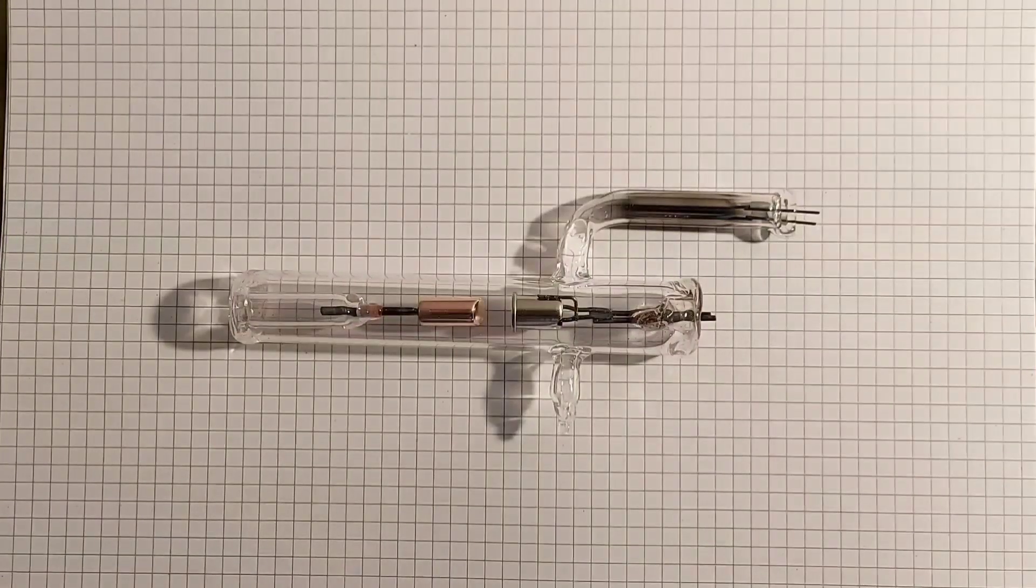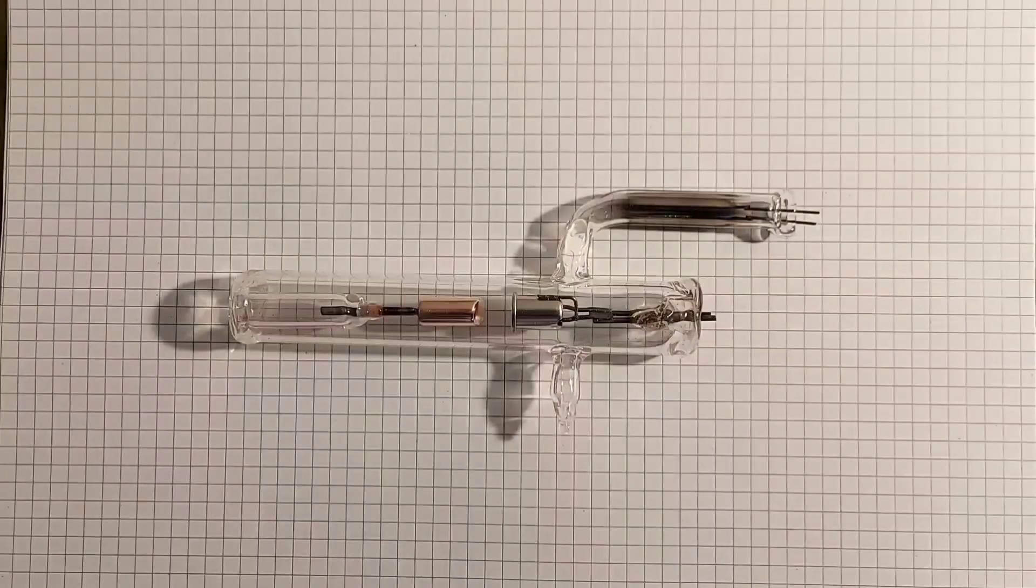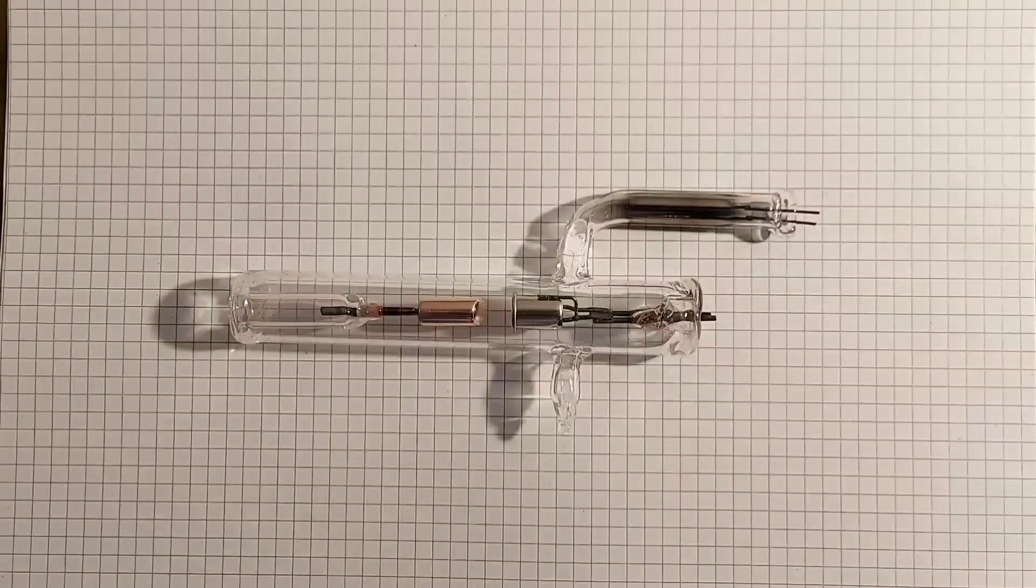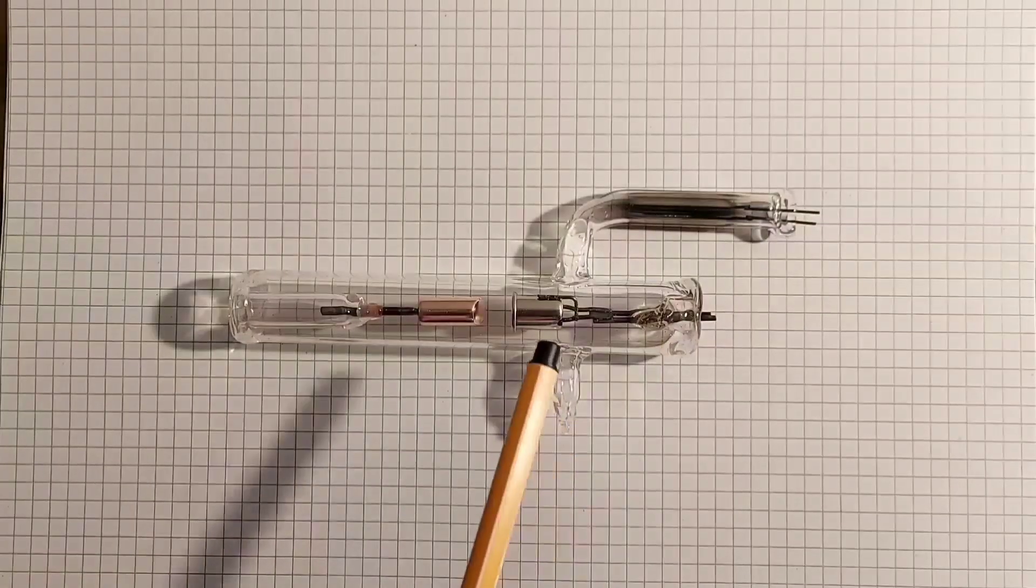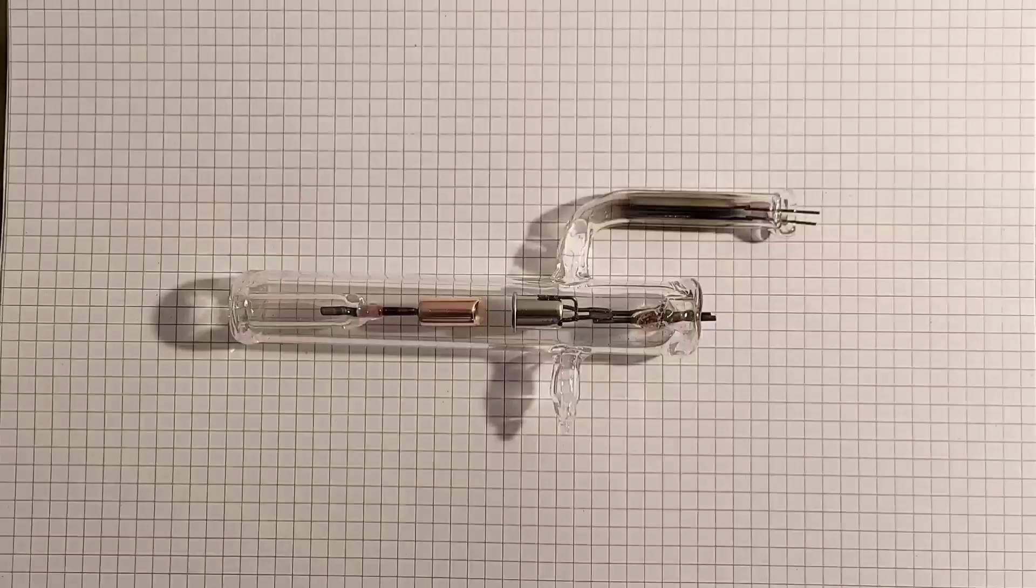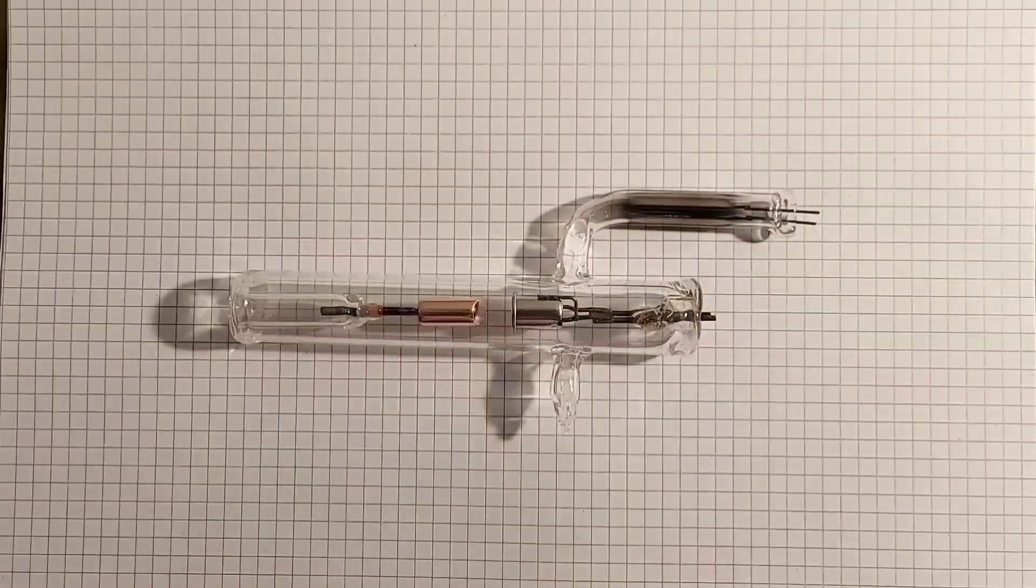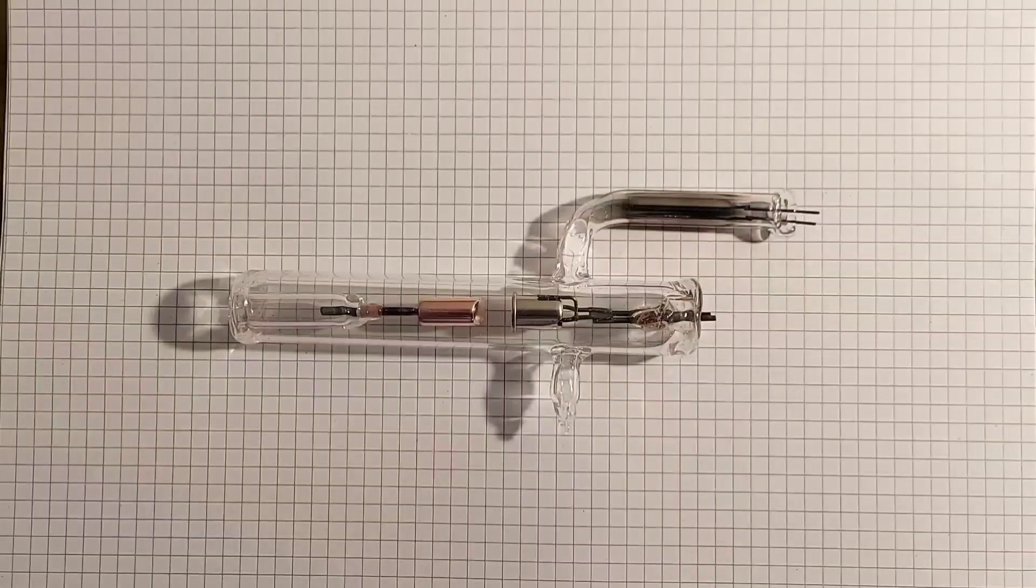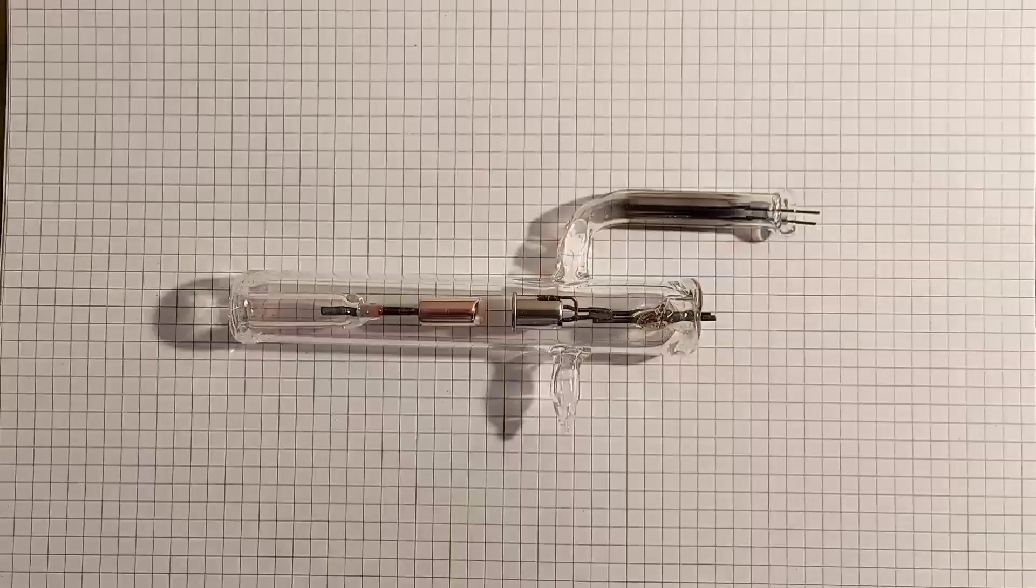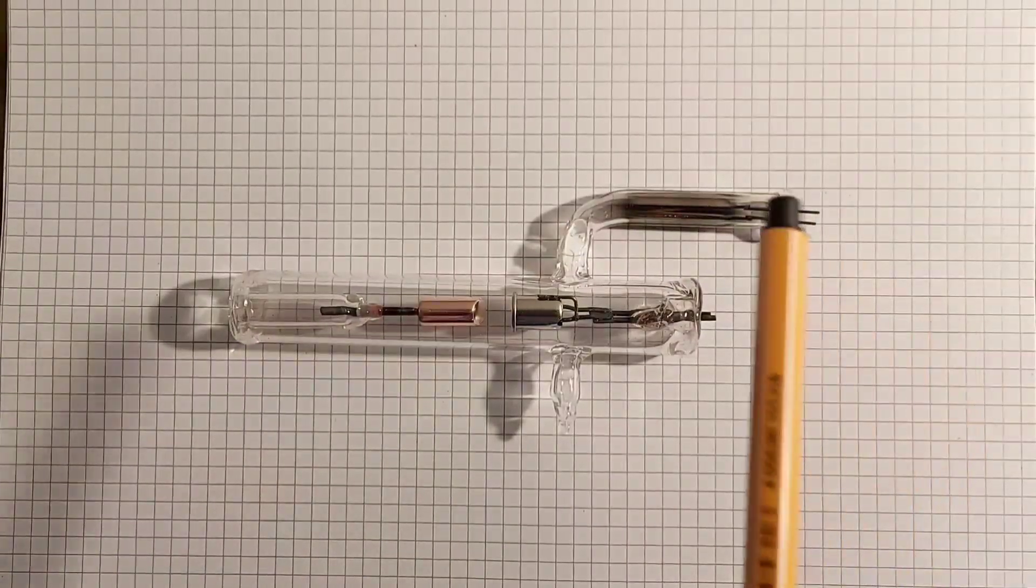So my tube is a hot cathode x-ray tube and it means it uses thermionic emission of a heated tungsten wire. You can also see a Wehnelt cylinder here. It's to help focusing the electron beam onto the target here. It's a copper target.